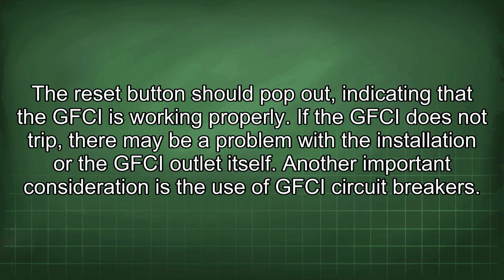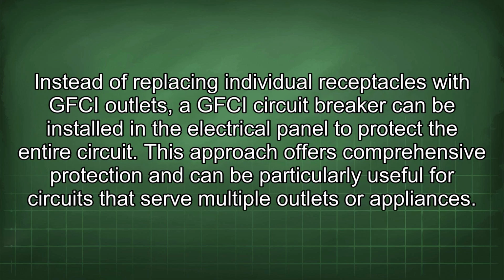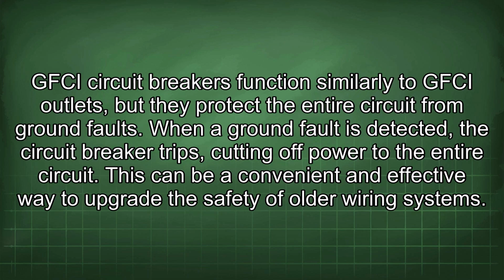Another important consideration is the use of GFCI circuit breakers. Instead of replacing individual receptacles with GFCI outlets, a GFCI circuit breaker can be installed in the electrical panel to protect the entire circuit. This approach offers comprehensive protection and can be particularly useful for circuits that serve multiple outlets or appliances. GFCI circuit breakers function similarly to GFCI outlets, but they protect the entire circuit from ground faults.